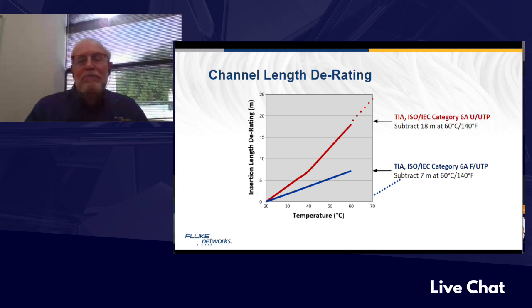Here's a troubleshooting tip: if you have a 330-foot or 100-meter run and you're seeing inconsistency, bad data, slowdowns, or high packet loss, double check that the cables weren't run right over the boiler or through outside aluminum shielding where heat builds up and could derate the cable. You may never notice it, but that's an important thing to check.